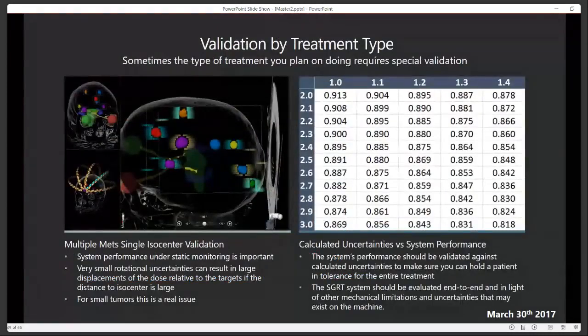And finally, a validation of the treatment types that you're going to be using. If you are a believer in multiple MET, single isocenter treatments, validation of that you can do mathematically. If you look at the table on the right, the vertical column is the distance from isocenter. The column across the top is the rotational uncertainty around one of the three axes.